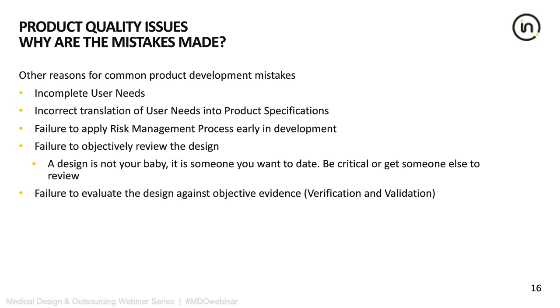Failure to evaluate the design against objective evidence during verification and validation is a place where we see many people fall down. They use subjective evidence, or they'll use limited sample sizes with people's viewpoints taken in, and it becomes anecdotal evidence and not truly objective evidence. And it leads them down a path where they're overconfident in the performance of the design and they don't recognize the issues until they actually launch the product. As I mentioned, failure to test or inspect to an adequate sample size during validation or verification can lead you down a path. Sometimes you're lucky when you really want to have proof that it's a good product.